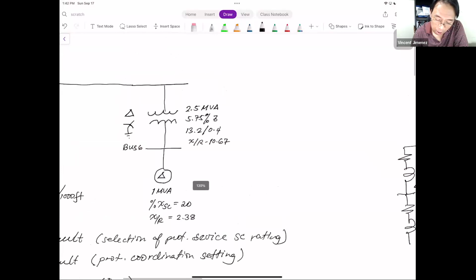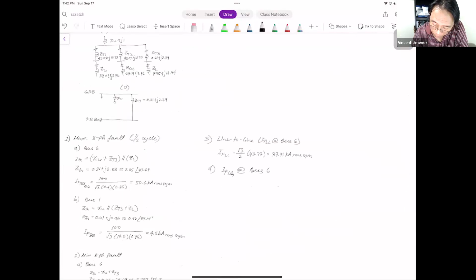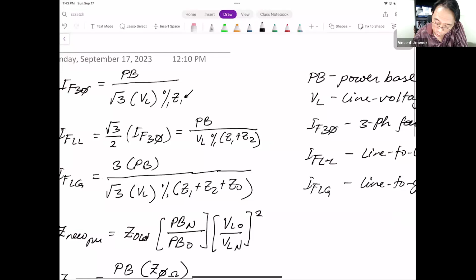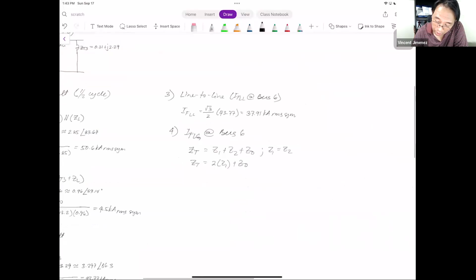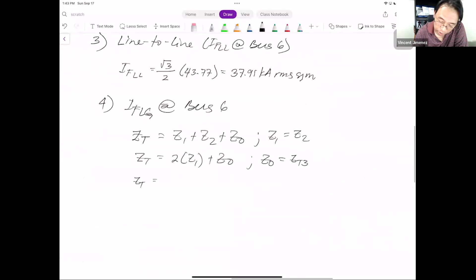So let's compute the total impedance. The formula is Z total equals Z1 plus Z2 plus Z0, as provided earlier. So IF line-to-ground equals Z1 plus Z2 plus Z0. Since Z1 equals Z2, no problem — therefore ZT can be said to be 2 times Z1 plus Z0. But what is Z0? From this diagram, Z0 is equal to ZT3. Therefore Z total is equal to twice Z1.